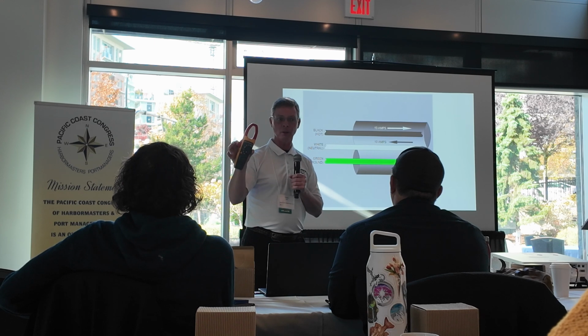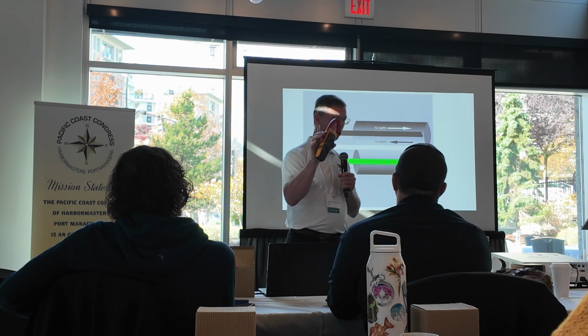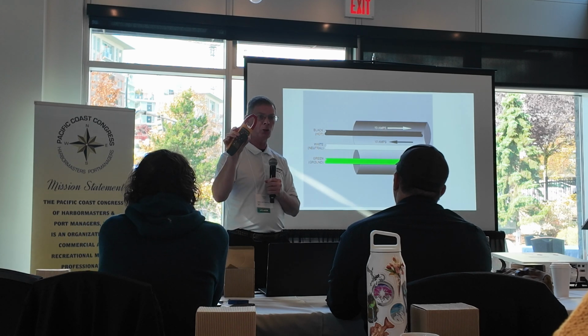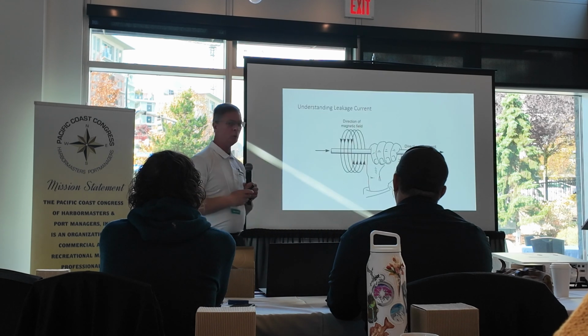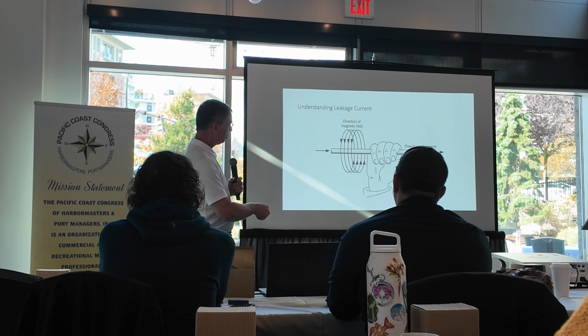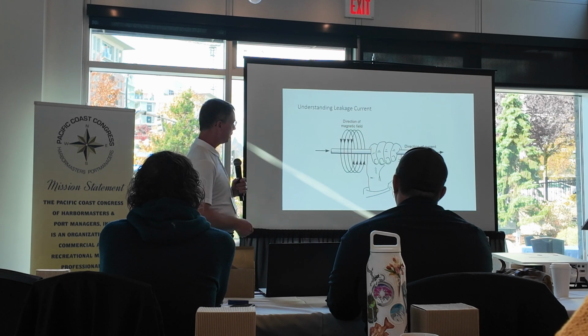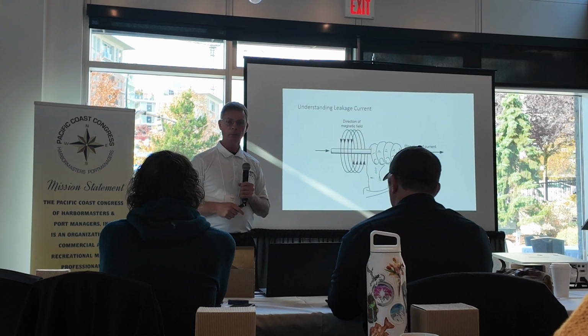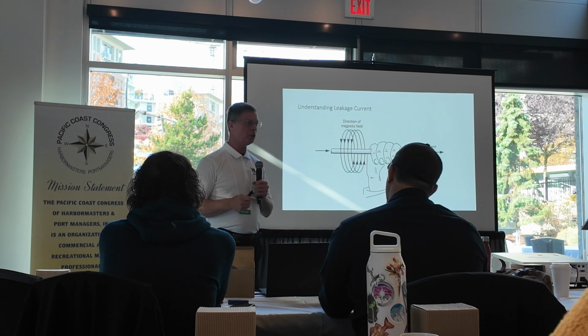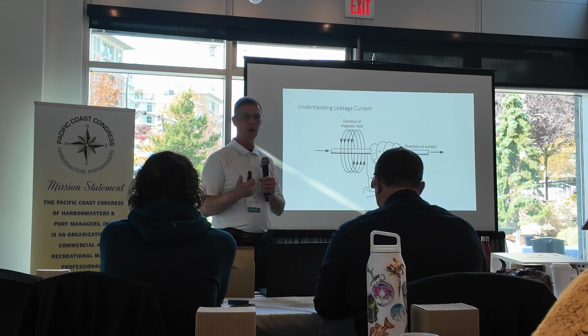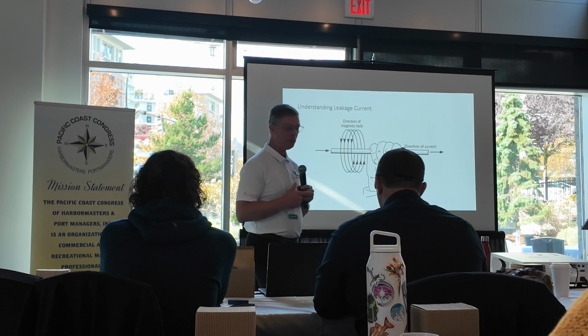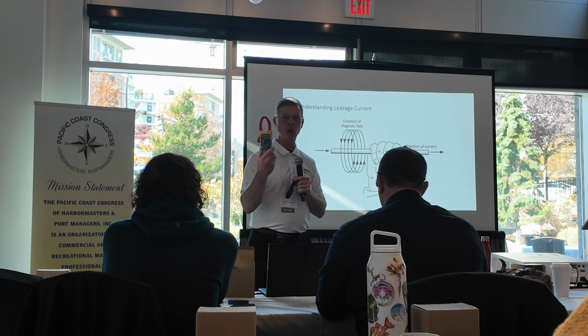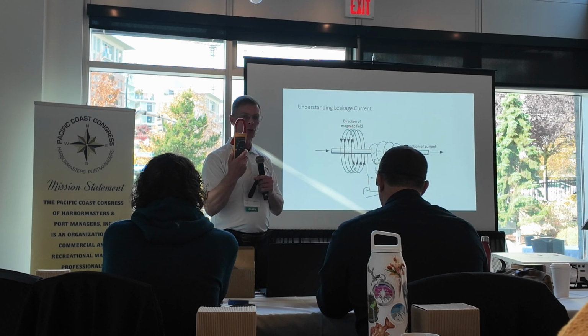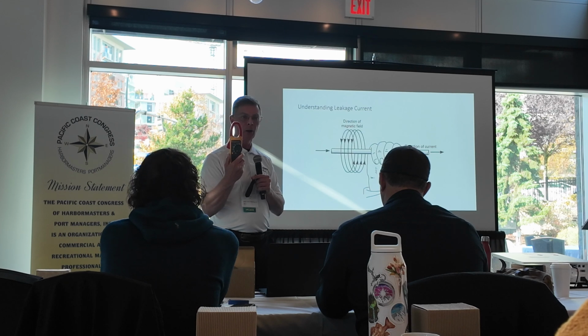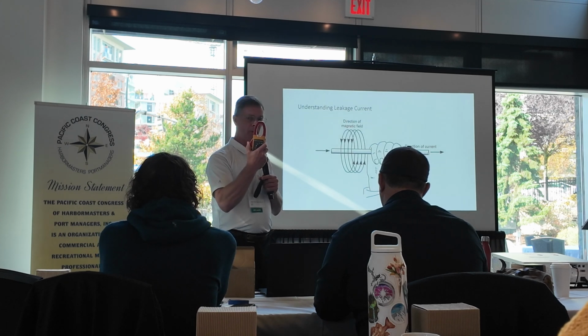Okay, that's perfect. Because it does not measure amps. There's no amps, no electrons running through this meter at all. It does not measure ampacity. Okay? There's a phenomenon called the right-hand rule. If you have a conductor and you put your thumb in the direction of the current and your hand wraps around the conductor, there's a magnetic field that goes around that conductor. It's a physical phenomenon in physics. That's just what happens. Every electron that goes through a conductor produces electromagnetic fields. So this meter is not measuring current, it's actually measuring the intensity of that magnetic field, and it's directly proportional to the amount of electrons going through that wire. So this is what it's measuring: magnetic fields.